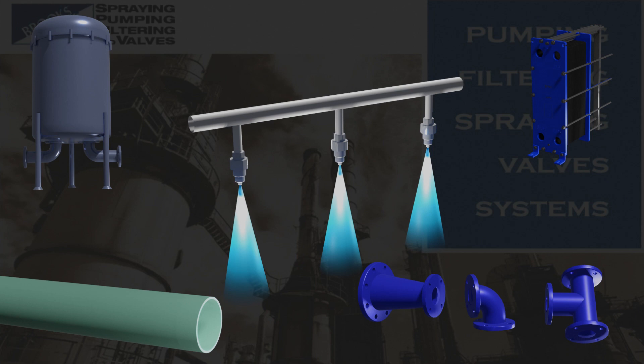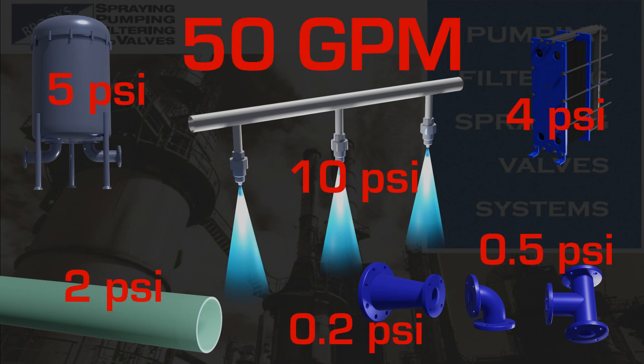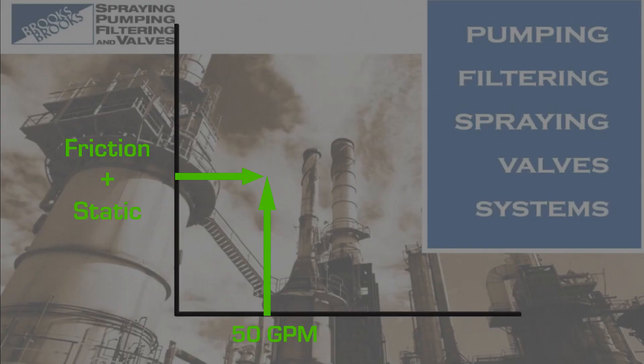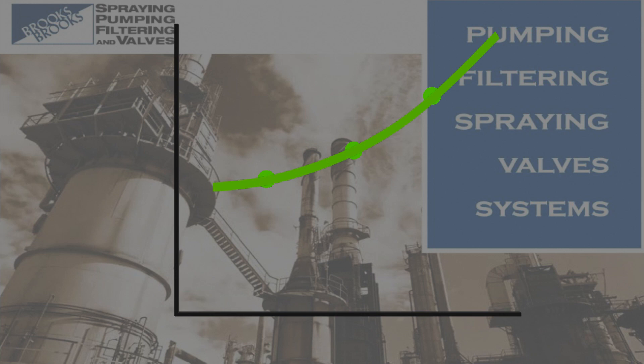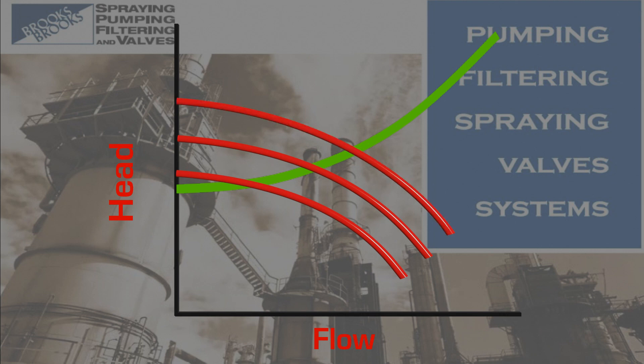Looking at the system as a whole, we can add the resistances together to get the total frictional losses. At a common flow rate — say 50 gallons per minute — sum each of the components' frictional losses together, then add the static head and plot this on the pump curve. Repeat this process for other flow rates. If we connect all these points with a smooth line, we will have a system resistance curve. Now we can estimate what pump speed or impeller diameter we should use to achieve a particular flow and head.